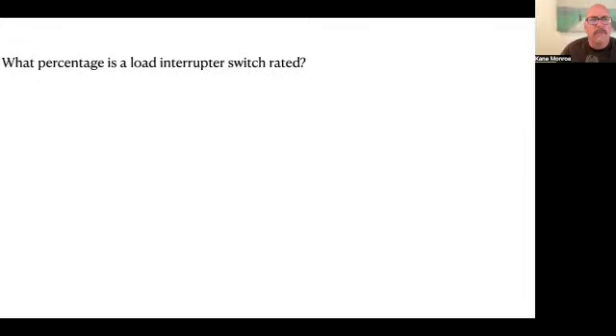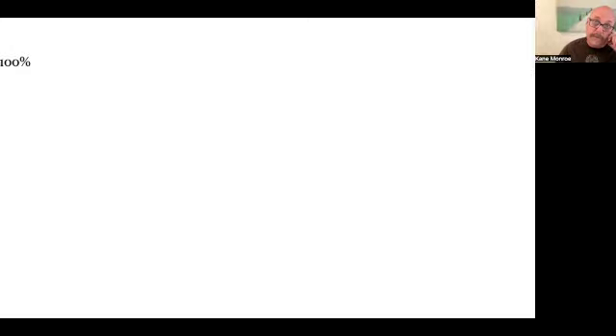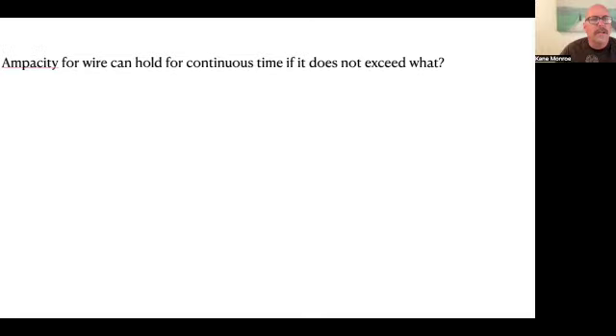Now, next one. What percentage is a load interrupter switch rated? At what percentage is a load interrupter switch rated? Ooh, that's a big one. So that is at 100%. So don't start derating to 80% or 125%. It's 100%. All right, next one.